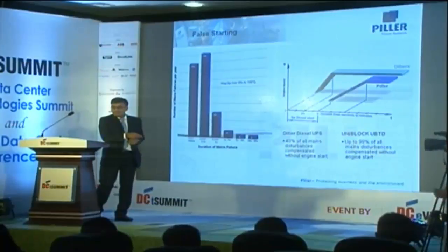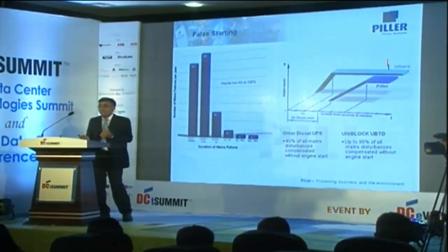This is a historical chart which shows the failures of power supply. It may not be applicable to Bangladesh, but globally this is applicable. Almost 96% of grid failures are less than 3 seconds. Only 4% of the grid failures are longer than 3 seconds. So if you have a system that can withstand this 3 seconds by not starting your diesel engine, your overall operating cost is much, much lower.